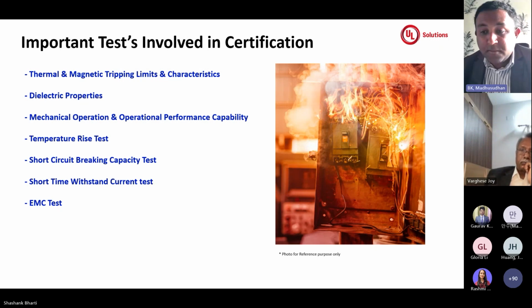Also, on the plastic parts, an additional glow wire test will be conducted to check the flammability of the material, and the standard gives clear guidelines: if there is a fire, then within 30 seconds of application we need to remove the temperature applied on the plastic part, and the fire has to extinguish within 30 seconds. These things will be looked at and documented during testing for plastic evaluations on the product for this category. So these are the major tests that will be covered for 60947 Part 2 for breakers during the testing and certification evaluation.